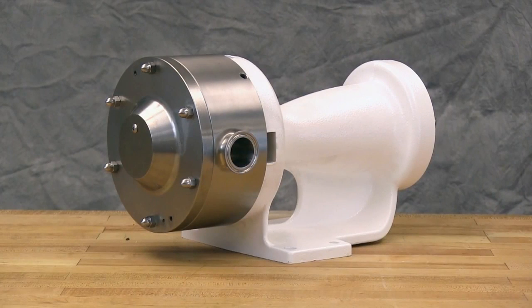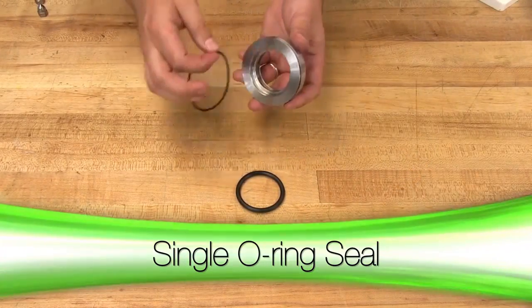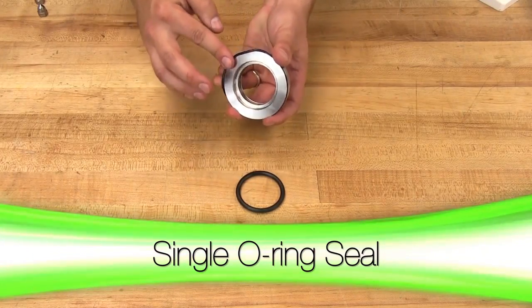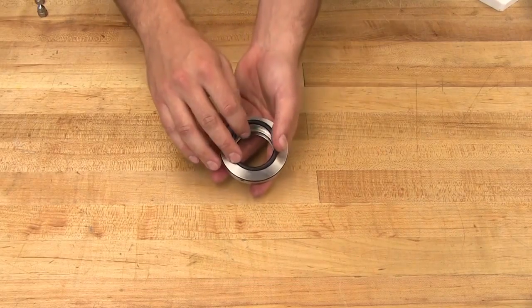It is recommended that new O-rings be used for reassembly of the pump. All O-rings should be lightly lubricated with a food-grade lubricant that is suitable for the application before installing. Install the two seal housing O-rings into the seal housing. The O-rings need to be installed on the side of the seal housing that does not contain the anti-rotation cutout.